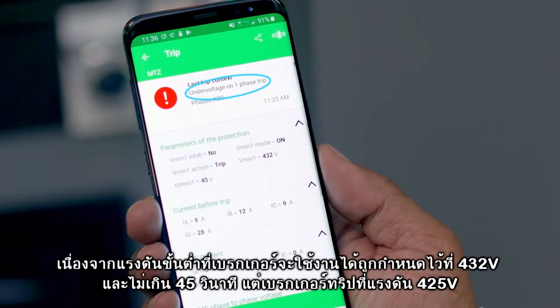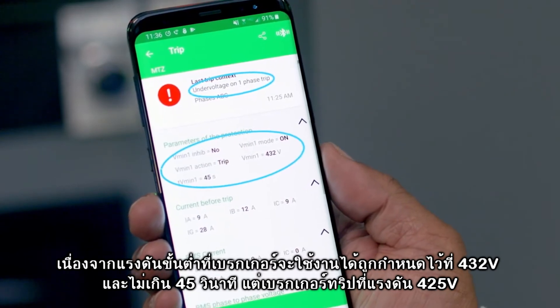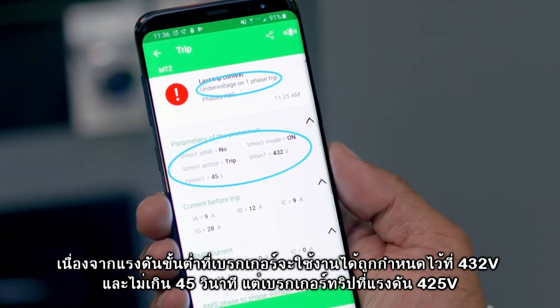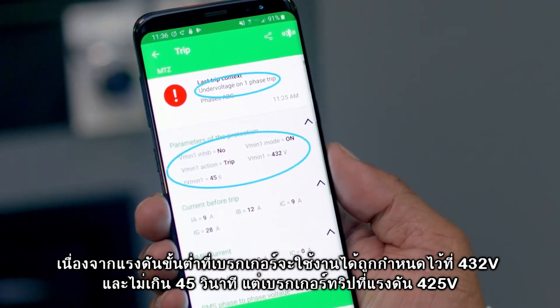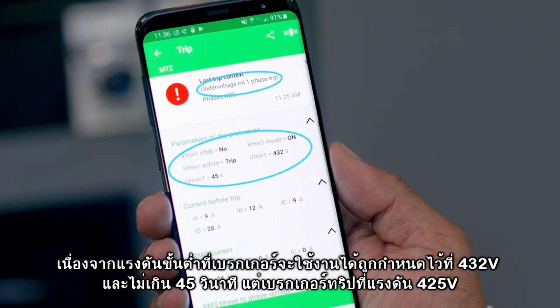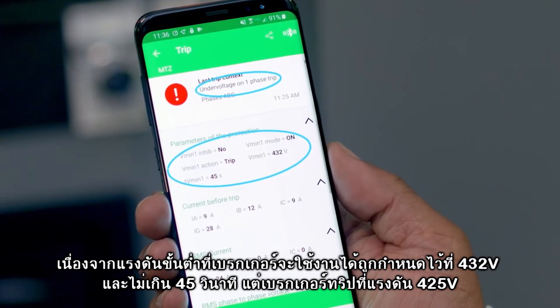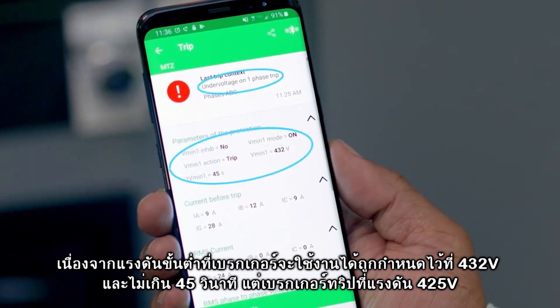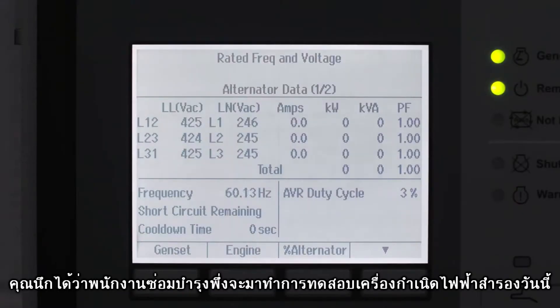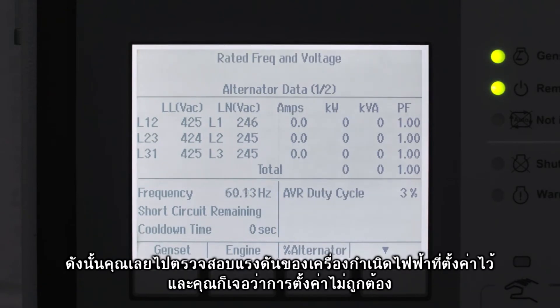The voltage threshold was set to 432 volts for 45 seconds and the circuit breaker tripped at 425 volts. You recall that the maintenance staff was doing a backup generator test today, so you double-check the generator voltage, quickly spotting it was set incorrectly.